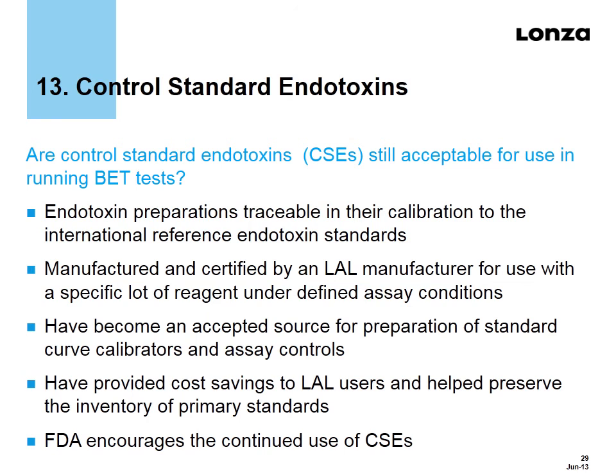Finally, the guidance document goes on to discuss controlled standard endotoxins and their use, and the question is, are controlled standard endotoxins, or CSEs, still acceptable for use in running BET assays? Controlled standard endotoxins are endotoxin preparations traceable in their calibration to international reference endotoxin standards, such as those found in the United States Pharmacopoeia, or EP. They're manufactured and certified by an LAL manufacturer for use with a specific lot of reagent under defined assay conditions.